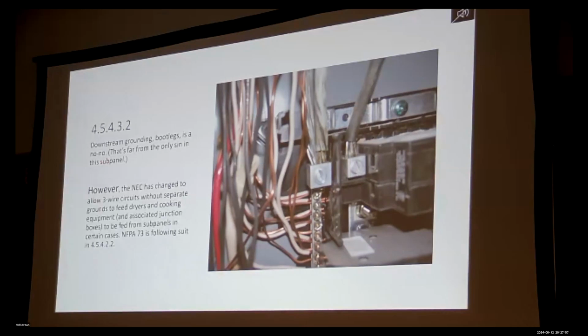But if there is a main panel and it's converted to a subpanel and it feeds an oven, a dryer, and feeds it through service entrance cable, SE, which combines the neutral and the ground, well, you have downstream grounding. Just like you have when you have a bootleg receptacle.